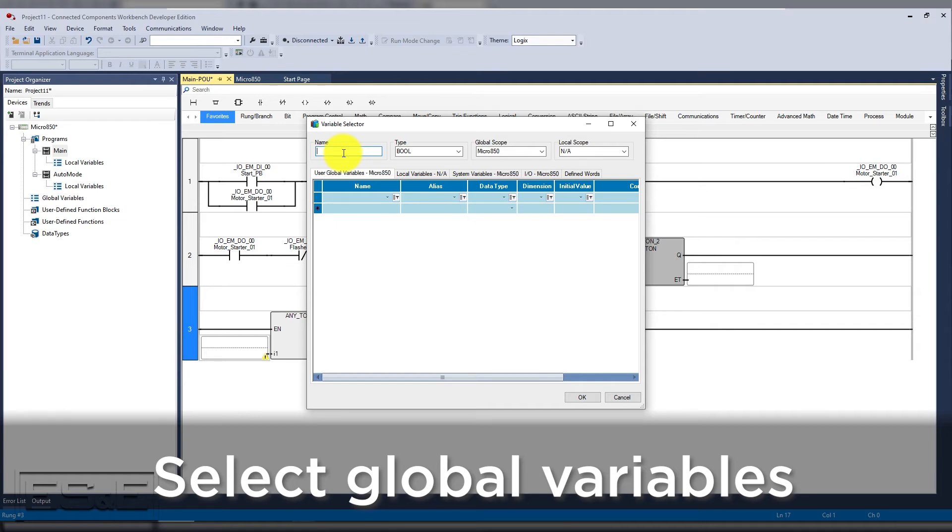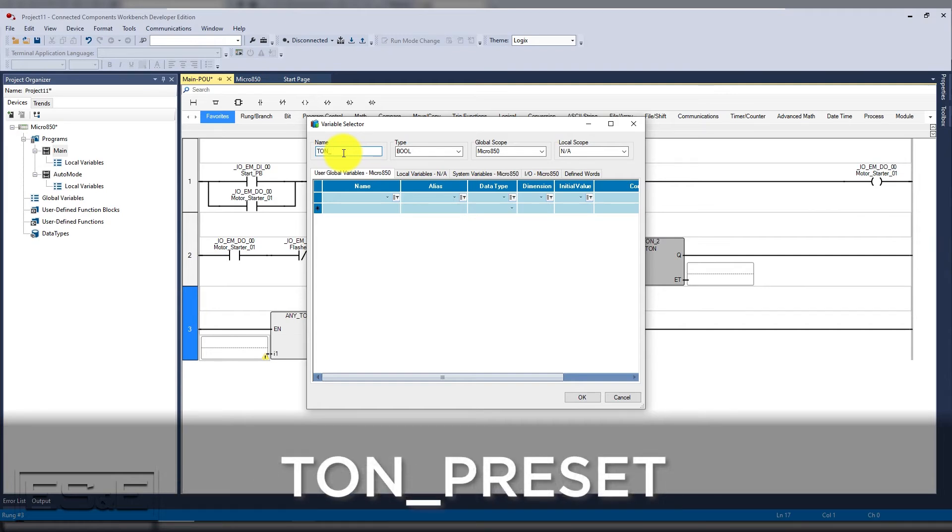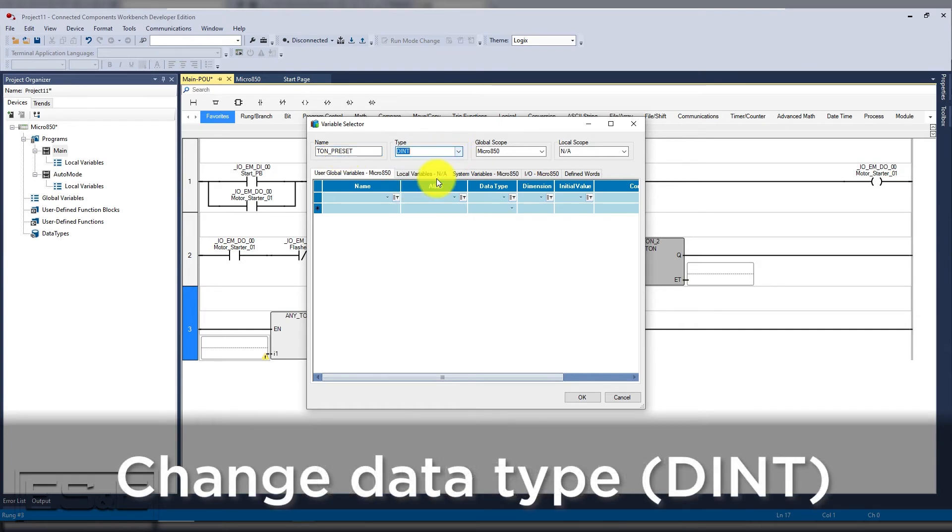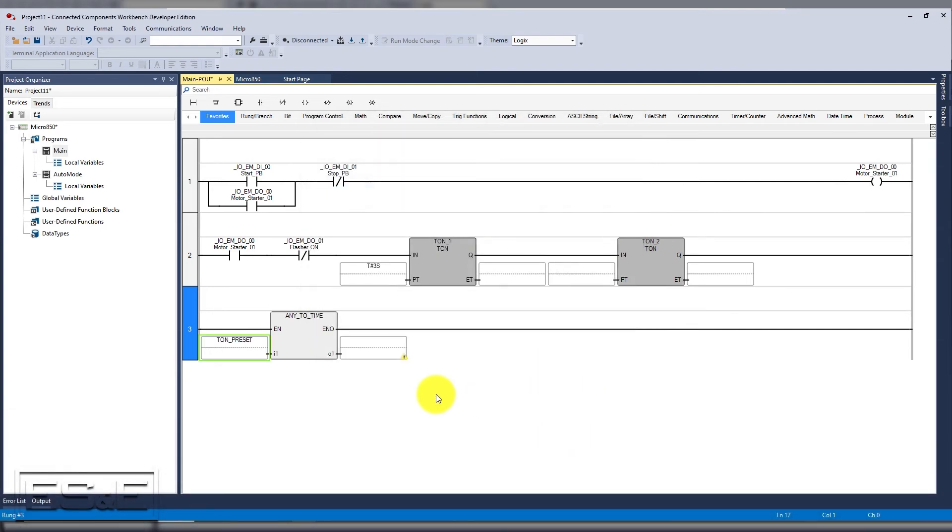We don't want to use the local variables because they cannot be addressed from the HMI. Once on the global variable, we can then create a new tag called timer on preset or TON_preset and then change the data type to DINT or double integer.